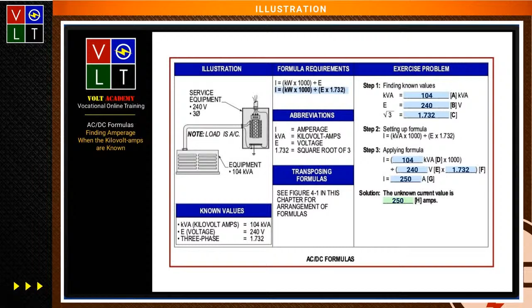So if I come back and look at this, what was my amperage here? 250 amps, giving me 104 kVA. Moving forward, I've got 250 amps like I've been doing, 240 volts, and 1.732 for the 3-phase. I multiply all those, divide by 1,000, and what's my kVA? 104. Yep, so this proves it doesn't really matter to me. It just depends on what known values you have, and based on those known values, you're seeing it's the same. It just depends what value you're trying to find and what information's available to you.